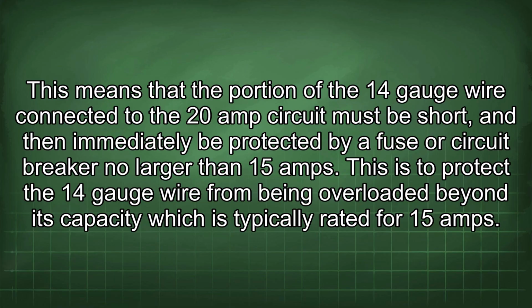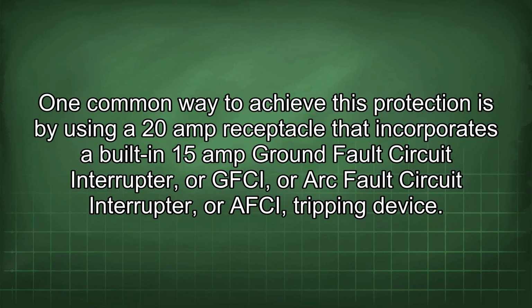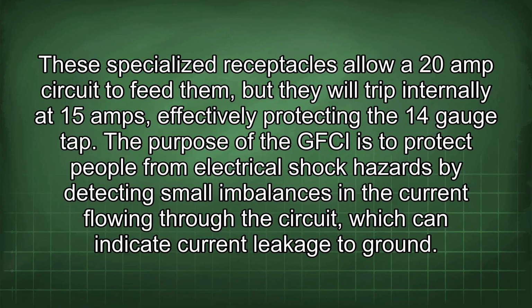This is to protect the 14-gauge wire from being overloaded beyond its capacity, which is typically rated for 15 amps. One common way to achieve this protection is by using a 20-amp receptacle that incorporates a built-in 15-amp ground fault circuit interrupter, or GFCI, or arc fault circuit interrupter, or AFCI tripping device. These specialized receptacles allow a 20-amp circuit to feed them, but they will trip internally at 15 amps, effectively protecting the 14-gauge tap.